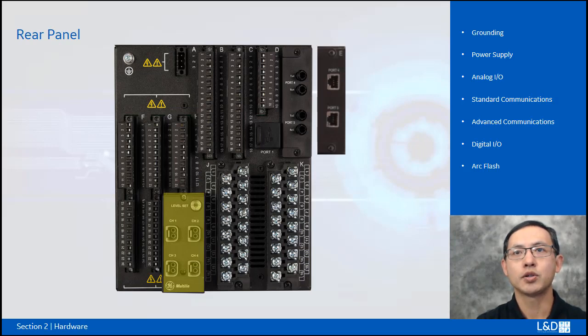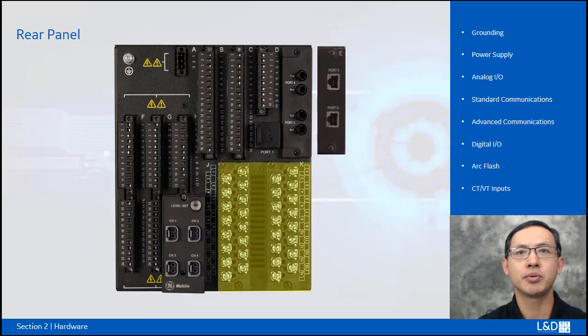Depending on the order code, slot B and C can be used for digital inputs. So the maximum configuration can be up to 23 digital outputs and 60 digital inputs. Bottom right side is the CT-VT inputs, which can be configured up to 8 CT and 8 VT for differential protection of motor, transformer, or generator, or dual feeders of 850D.